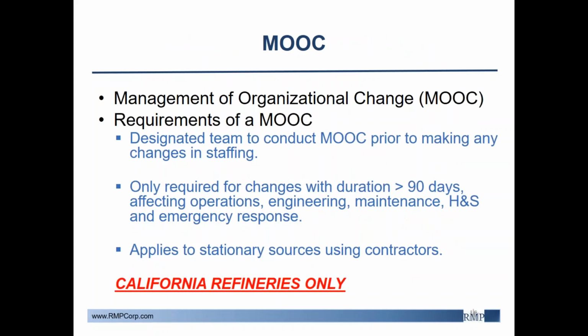Thank you, Morgan. Management of organizational change, also known as MOOC, requires its own documentation and procedures. The following requirements, according to a quote directly from the regulations, state that the owner or operator shall designate a team to conduct a management of organizational change assessment prior to reducing staffing levels, reducing classification levels of employees, changing shift duration, or substantively increasing employees' responsibilities at or above 15%.